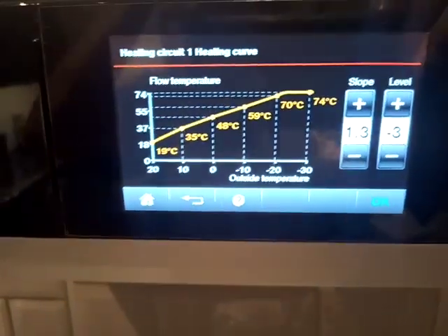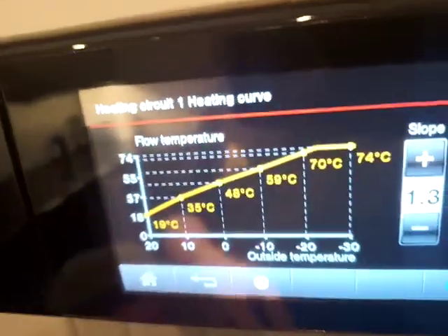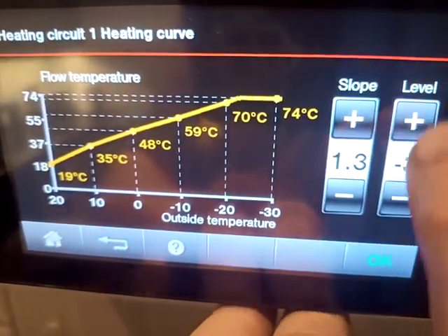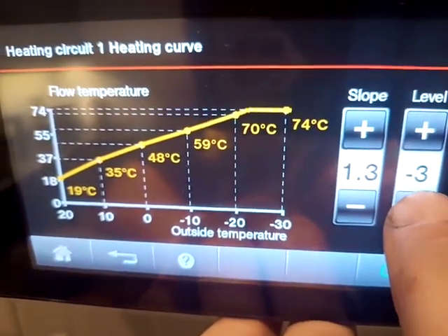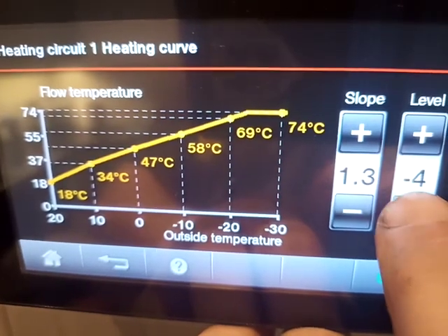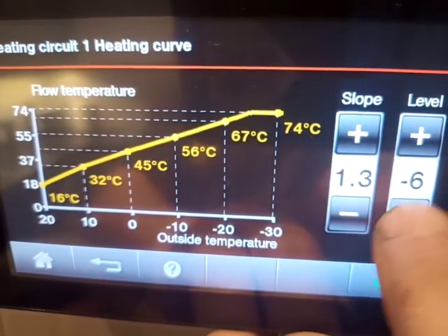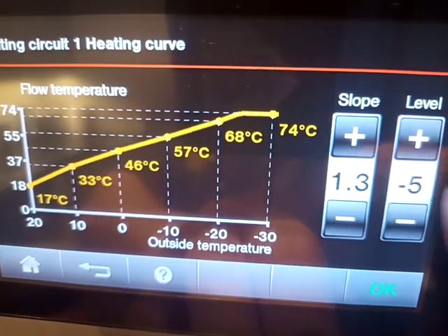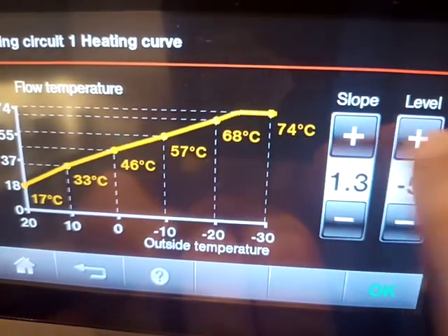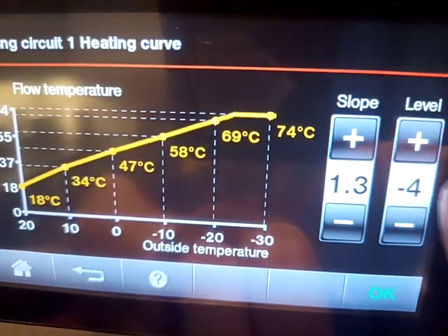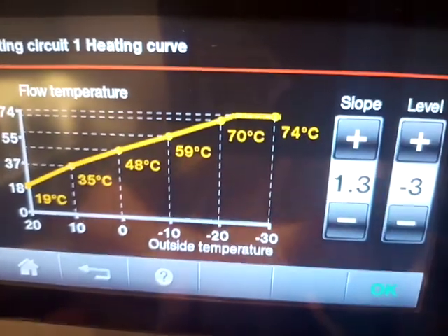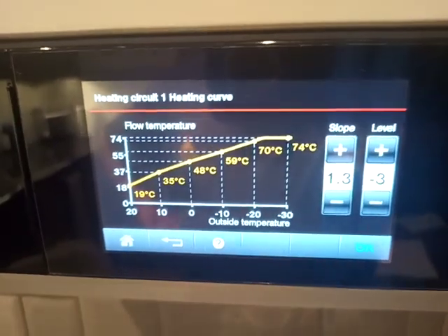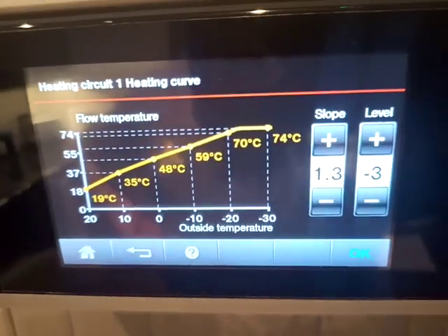Right, okay. When you adjust temperature for the system, the target temperature, actually what you're doing is adjusting level. So if I was to turn down the temperature, I would simply be shifting the entire slope, as so. This isn't easy through a camera. There you go. Right, okay, got there. And that's about all that can change on there.